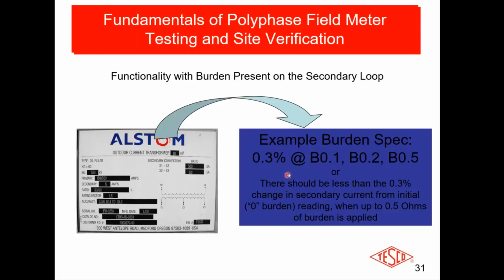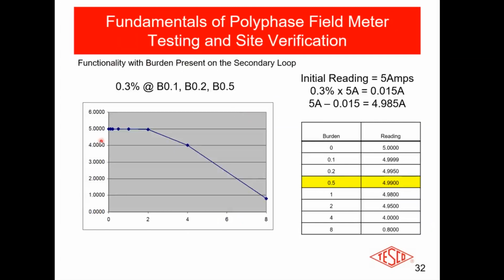This is an Alstom transformer here, and it tells you right on the faceplate, 0.3% at a burden of 0.1, 0.2, 0.5. So up to half an ohm, this is going to maintain its accuracy. What happens after that? So here it is, 2 ohms, 1 ohm, half an ohm. It's very good, okay? It's supposed to be a something to 5, and I'm getting 5 amps out of it. In fact, I'm actually getting 5 amps as I pass 1 ohm. As I get 2 ohms, I'm just a little bit less. You can see 4.99, 4.98 at 1 ohm, 4.95 at 2 ohms. So I've lost a little bit of accuracy, haven't I? Lost about 1% of accuracy here.